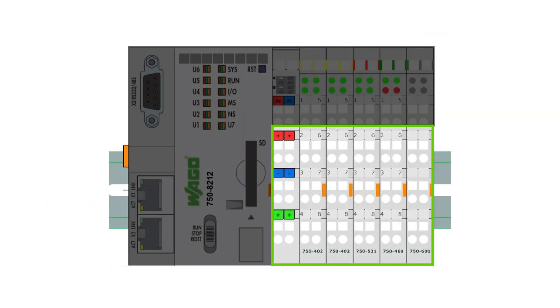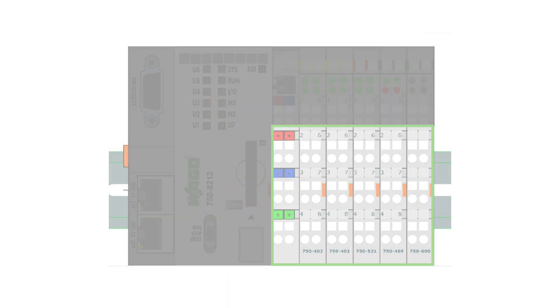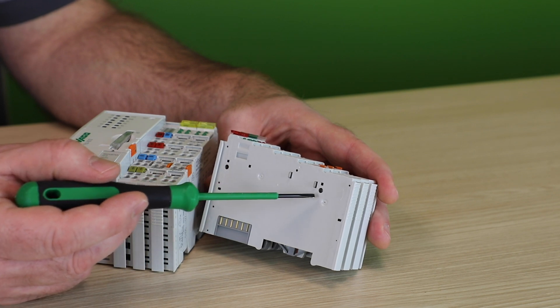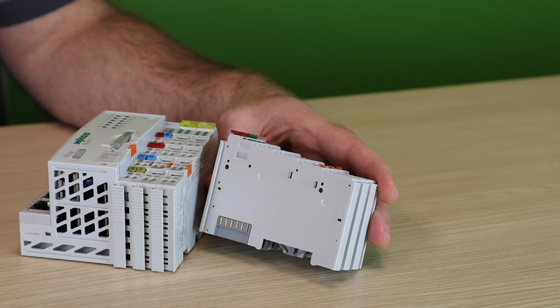Second, we have field side power. The majority of our I.O. modules require the presence of a field supply also. Typically, that would be a 24 volt DC supply. Simply provide another 24 volt DC power source and connect the positive to the plus plus and the negative to the minus minus of your supply module. Power jumper contacts will route the field supply down the node in most cases to the other I.O. modules.